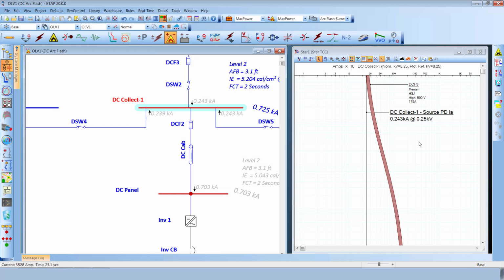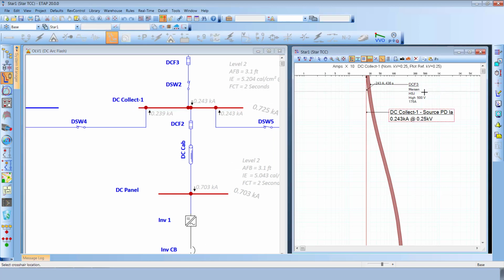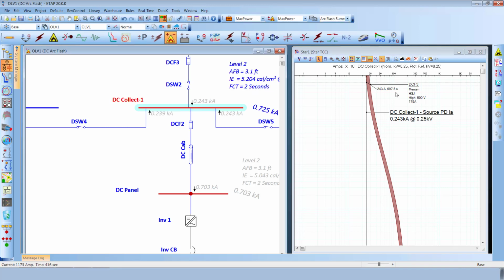Starting from ETAP 20, we have enhanced the program to show this source PD arcing current on the time current curve by enabling this calculated / user defined source protective device option for a given bus nominal voltage. And this clearly indicates that the total current seen by this particular protective device can obviously operate for a longer clearing time and hence cause a very high incident energy. In this case, the program still limits the clearing time to 2 seconds to avoid a high incident energy accumulation, and it is actually configured in the study case options as shown here.